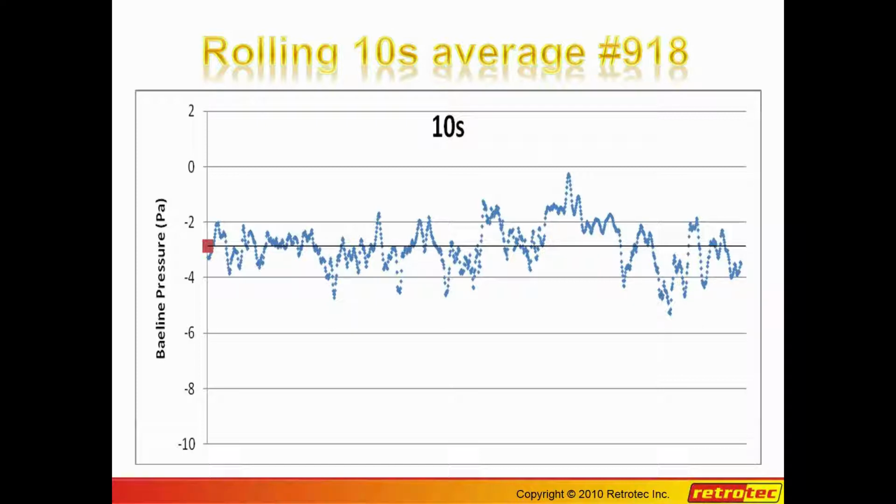And you can see here that we've gone from about 0 down to about -5, which, for testing at 50 pascals, is fully 10%. If we're doing a multi-point test and going down to, let's say, 15, that's going to affect our results massively.